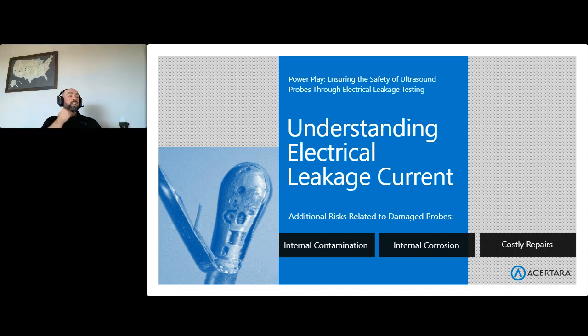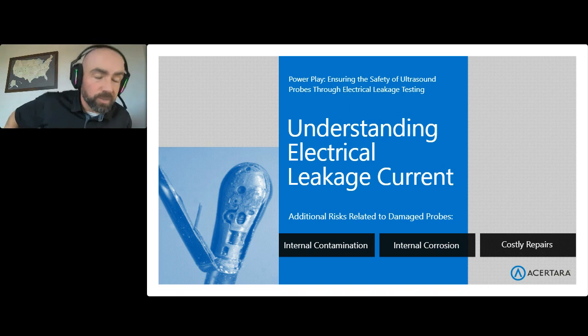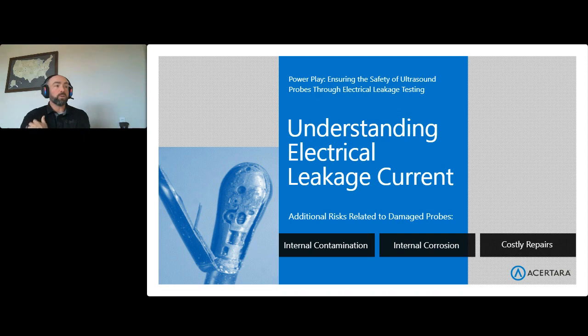Understanding electric leakage and current here. Patient electric shock is not the only hazard that's related to a damaged probe. Fluid ingress due to damage to the probe can lead to further damage to the probe, and can lead to pathogens entering the probe that cannot be properly cleaned or disinfected, and that can be a source of contamination for the next patient. Identify the damage, get that equipment out of circulation and get it repaired.